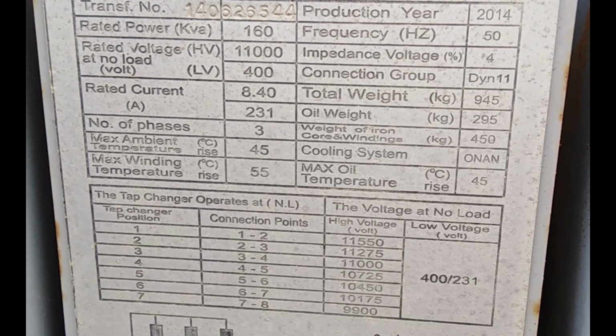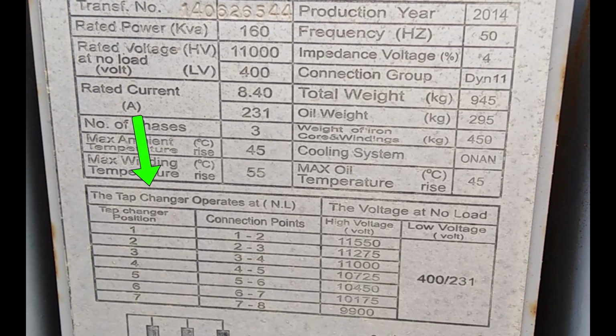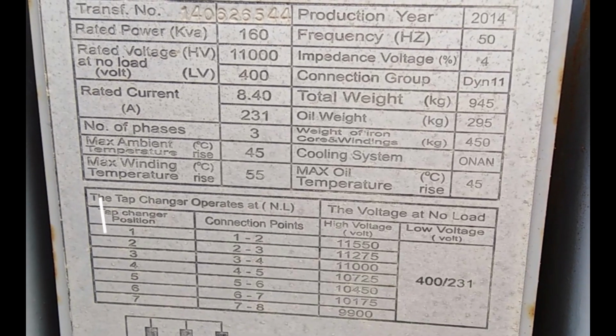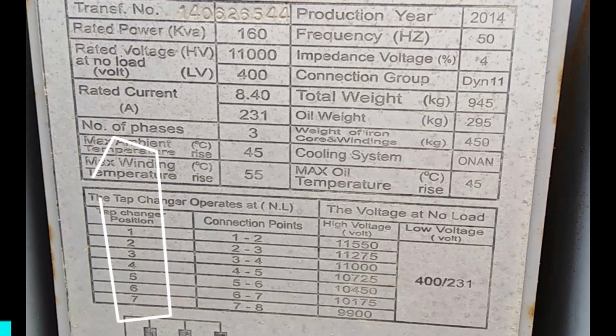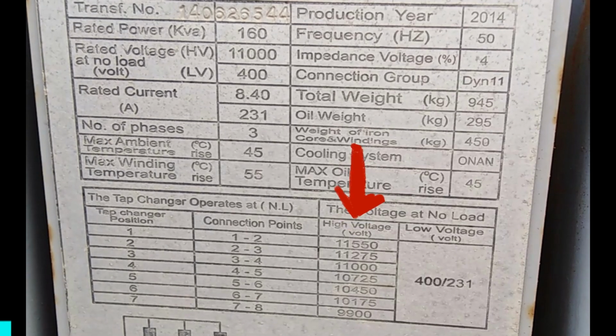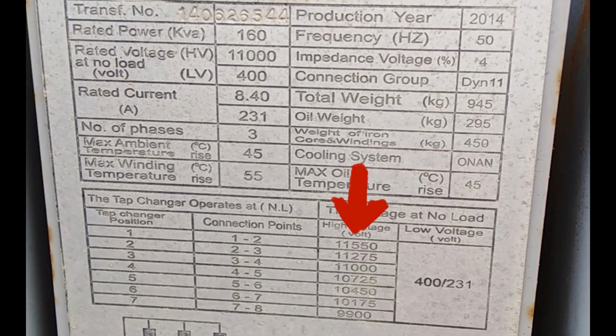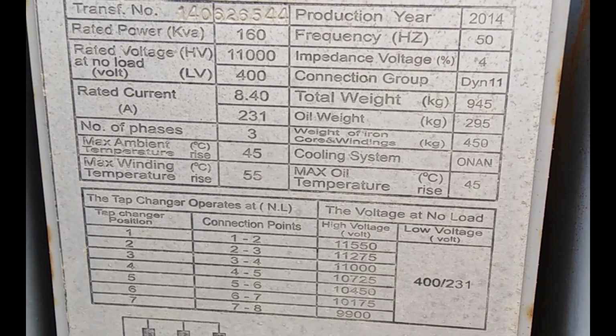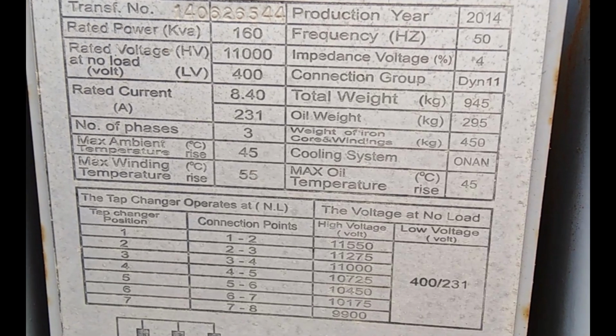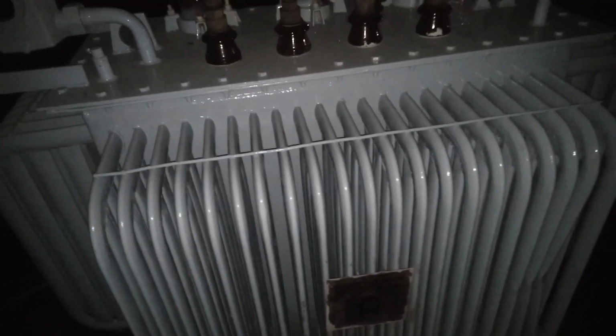Lastly, the tap changer data shows us that our transformer can adjust its voltage output with 7 taps, ranging from 11,550 volts to 9,900 volts, on the high voltage side. This flexibility is key for maintaining stable voltage levels, despite the demand changes or other system variations. And there you have it. Every piece of data on this nameplate tells a story about our transformer's capabilities, requirements, and how it keeps the lights on in our world.